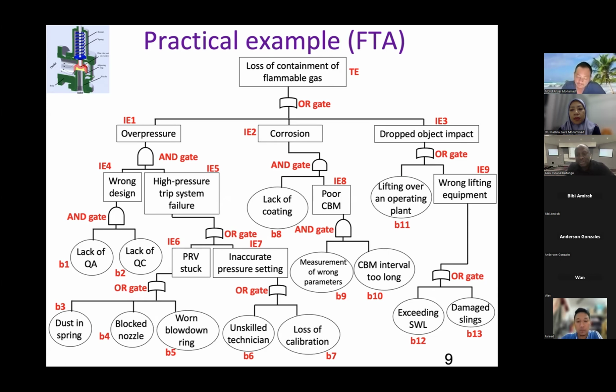That is well established. Here, for inaccurate pressure setting, you've come down to the technician not being skilled. So the decision is on you — do you want to fire the technician or train them? Those are action points. For loss of calibration, you just need to calibrate.